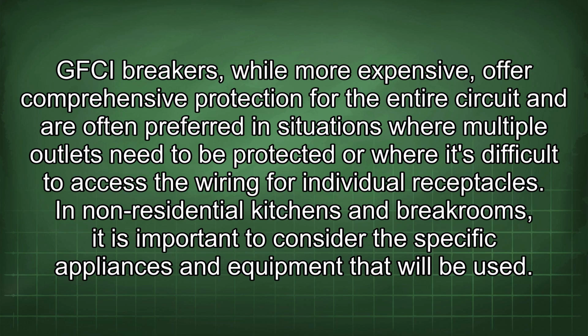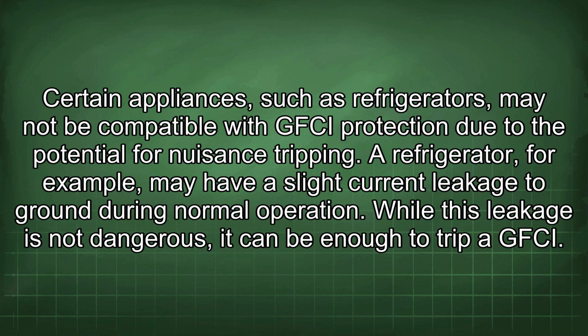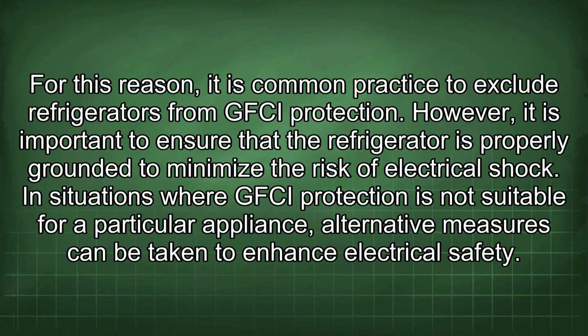In non-residential kitchens and breakrooms, it is important to consider the specific appliances and equipment that will be used. Certain appliances, such as refrigerators, may not be compatible with GFCI protection due to the potential for nuisance tripping. A refrigerator, for example, may have a slight current leakage to ground during normal operation. While this leakage is not dangerous, it can be enough to trip a GFCI. For this reason, it is common practice to exclude refrigerators from GFCI protection. However, it is important to ensure that the refrigerator is properly grounded to minimize the risk of electrical shock.